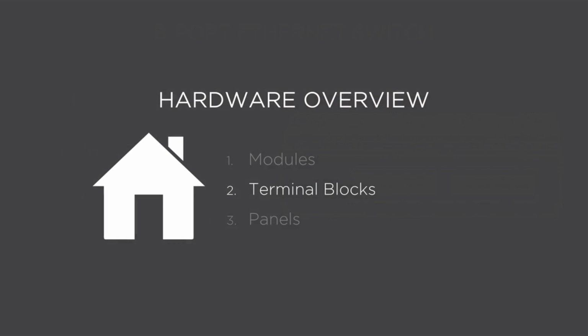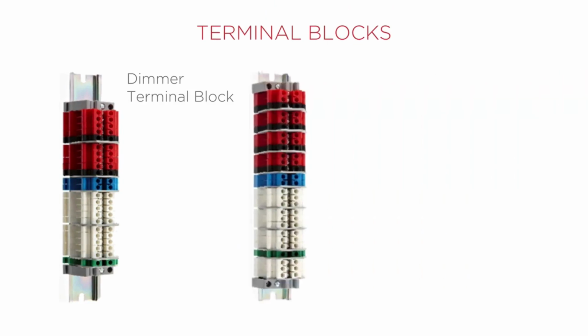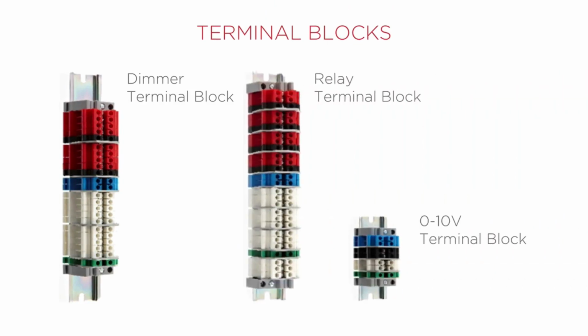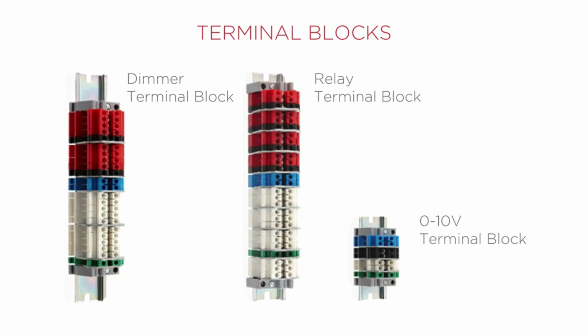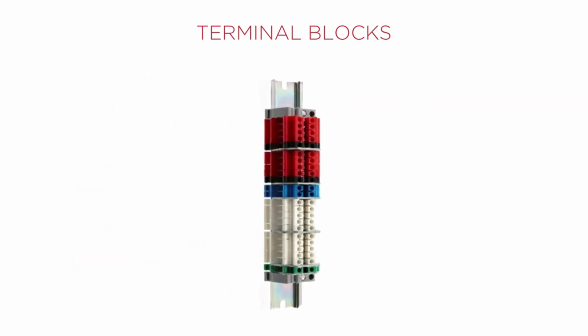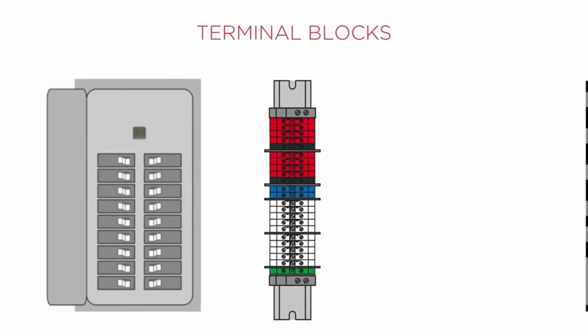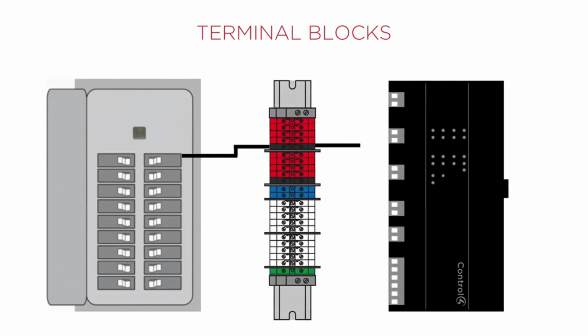Terminal blocks. There are 3 different terminal blocks, one for the dimmer module, one for the relay module, and one for the 0 to 10 volt module. Notice that the terminal block for the dimmer module has 2 black connections, one for each of the 2 lines in. Notice that the relay module has 4 black connections, one for each of the 4 lines into the relay module. The terminal block is the connection point between the circuit breaker and the module. It gives the electrician a location to terminate during pre-construction. Without the terminal blocks, wire nuts would have to be used instead.